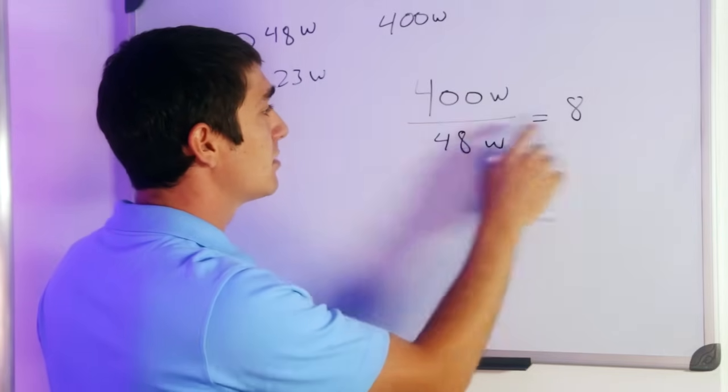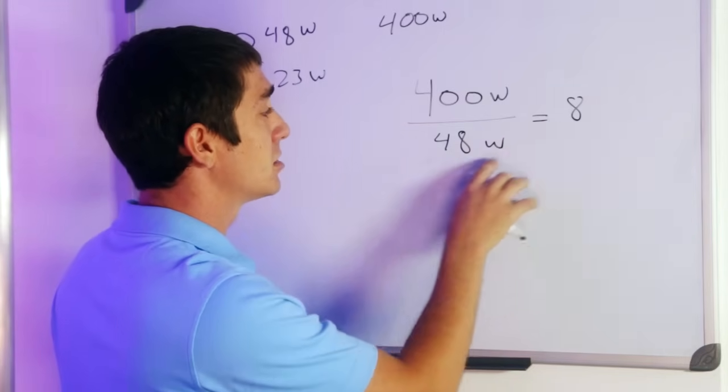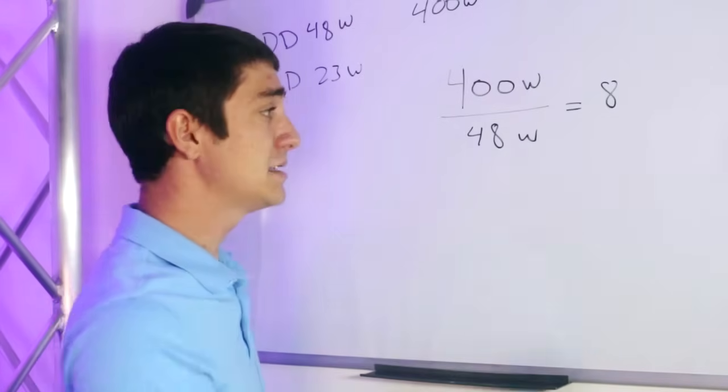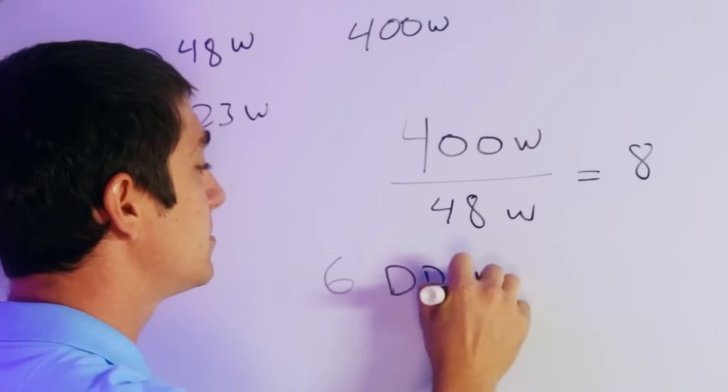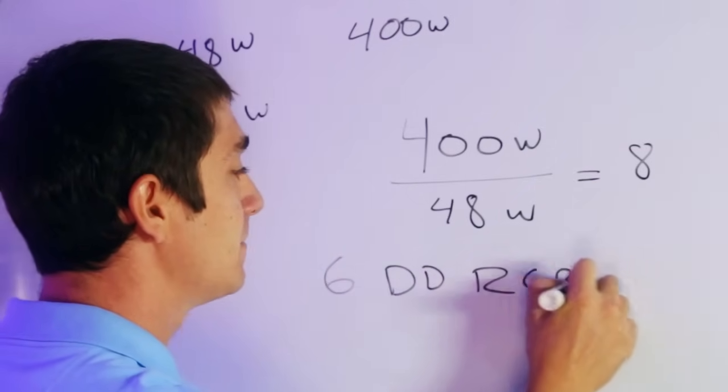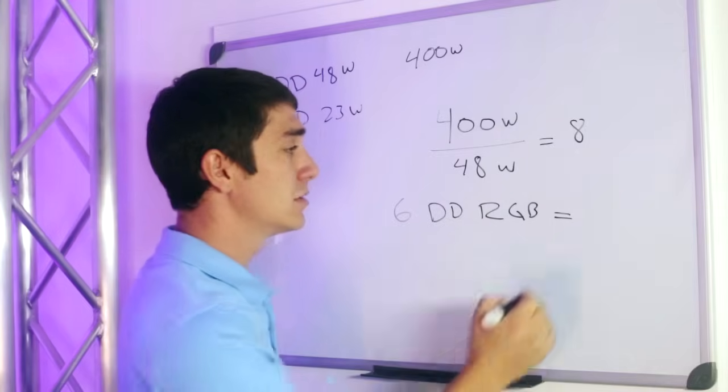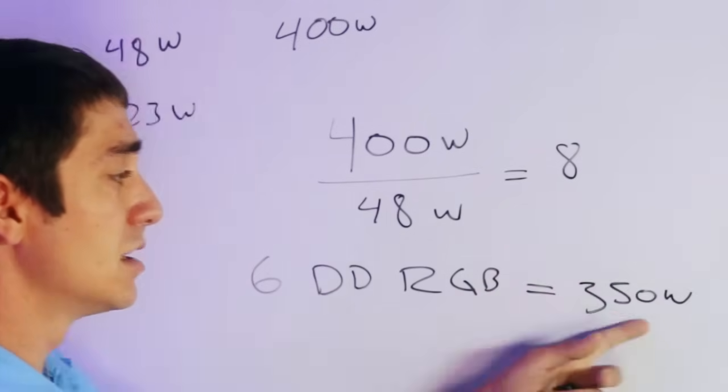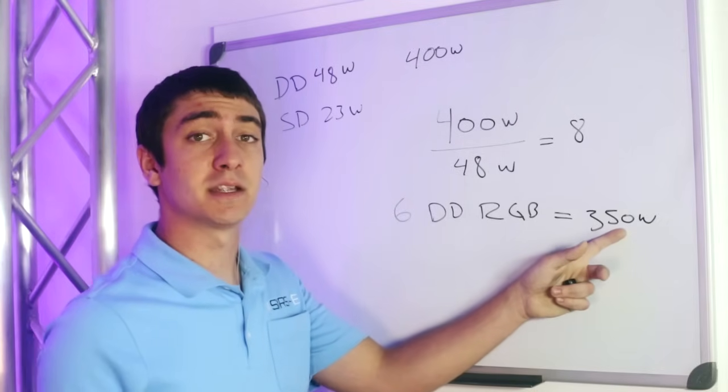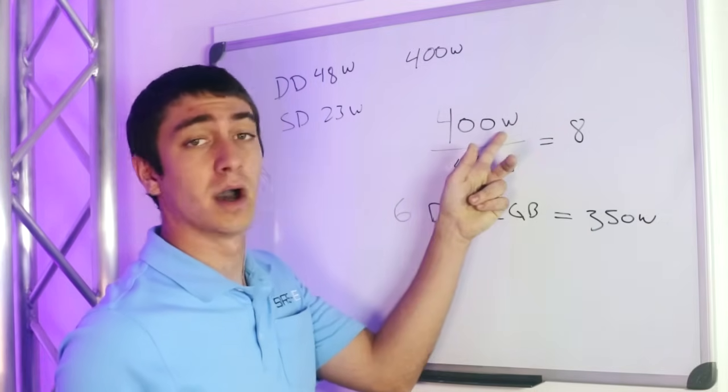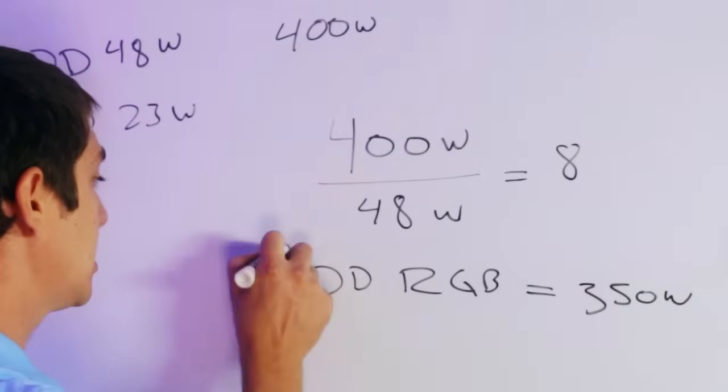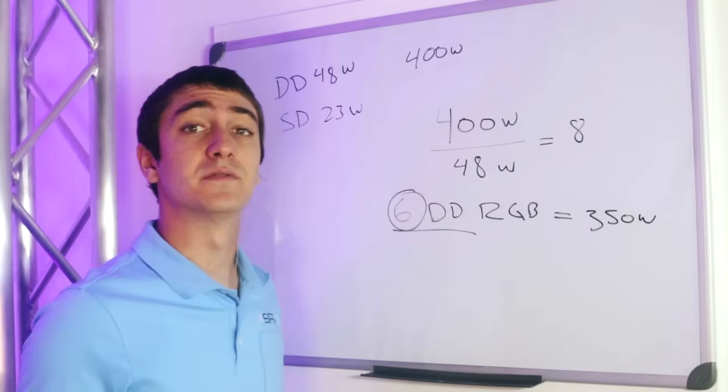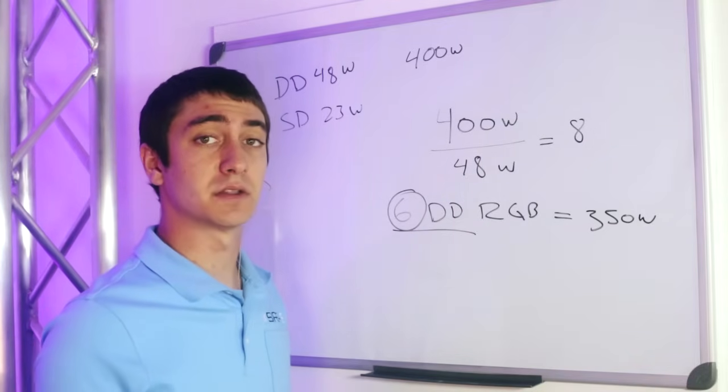So now that we know 8 is 100%, if we do 6 that will be 75% of the capacity. So if we do 6 dual density RGB strips, that will equal to right around 350 watts or so. That right there is about 75% capacity of the 400 watts, which will be perfect to run the strip at. So 6 strips would be the maximum that you can run safely without running into any issues.